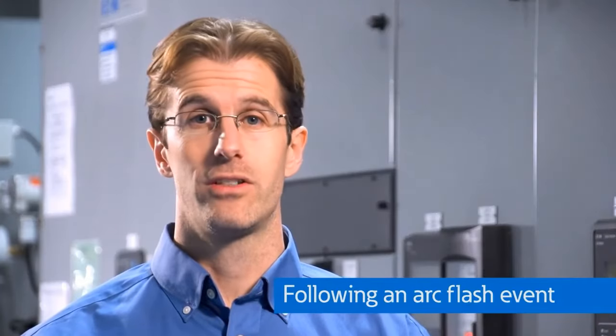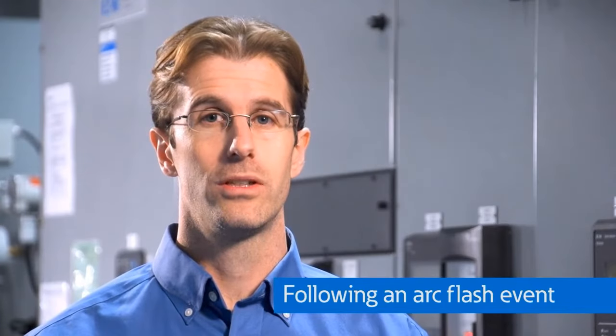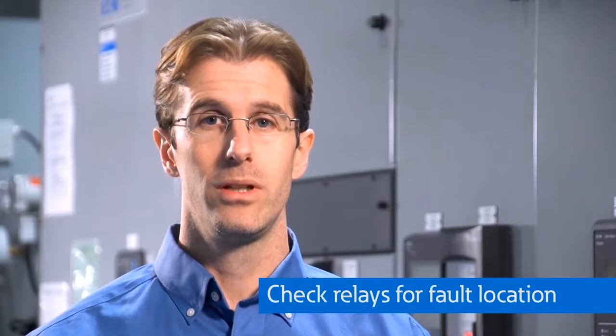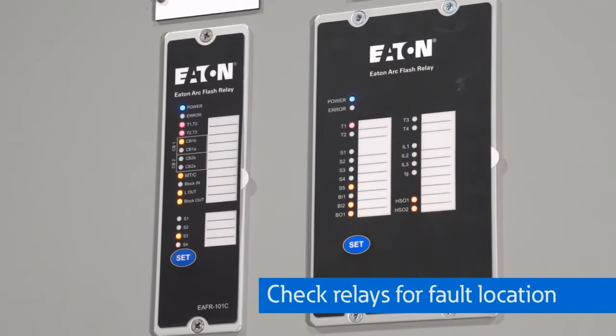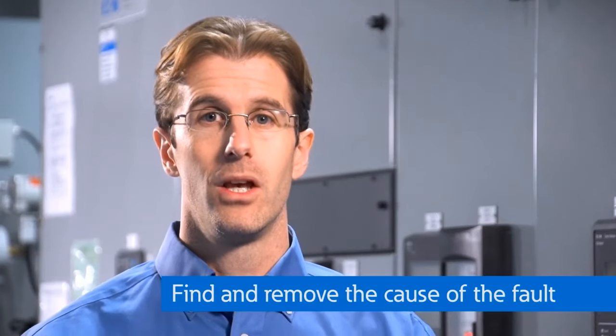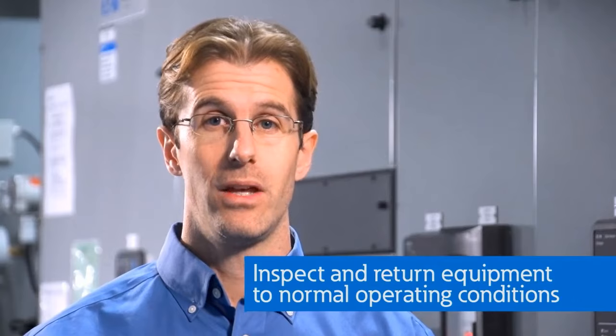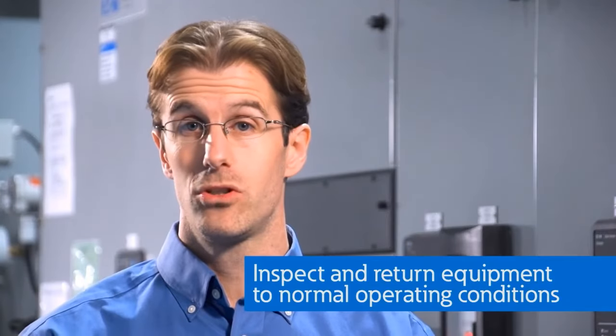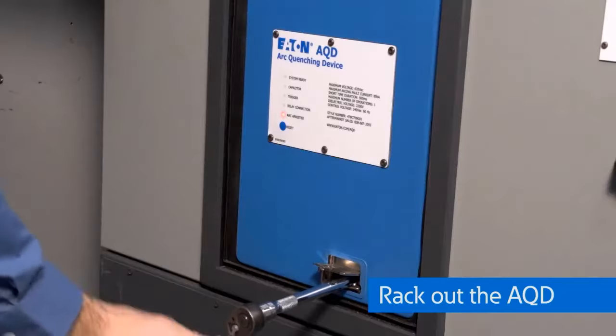So if you had an arc flash event, all you need to do is go up to the equipment, which is now de-energized. The relays will indicate which point sensors saw the arc flash, so you know where to go in the equipment to find the cause of the fault. You'll remove the cause of the fault and inspect the equipment, and then return it to normal operating condition, which should be relatively easy, since the equipment will be protected from damage due to the quick reaction of the arc quenching system. And then you'll rack out the arc quenching device.